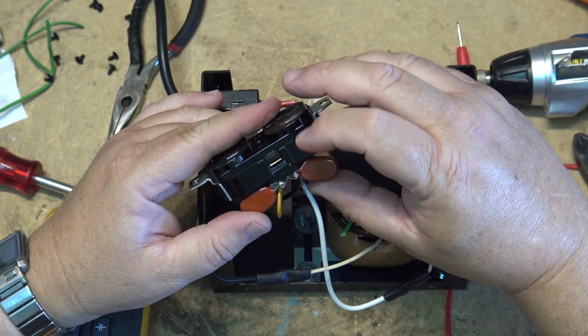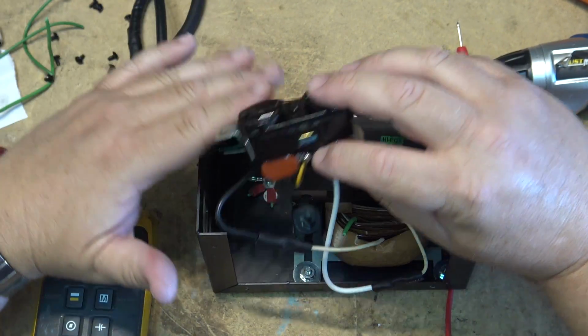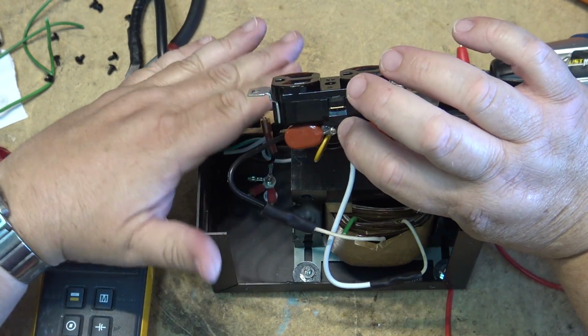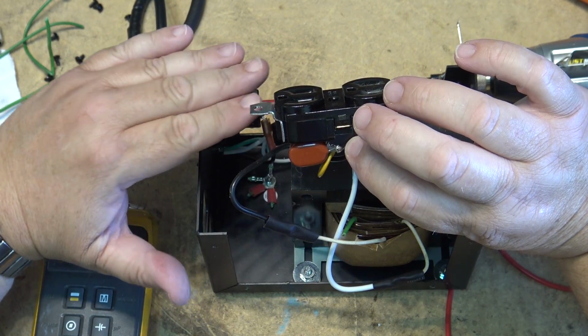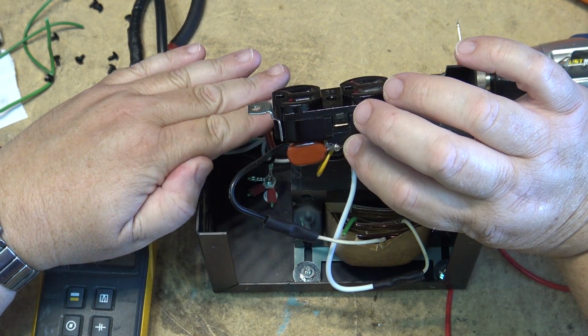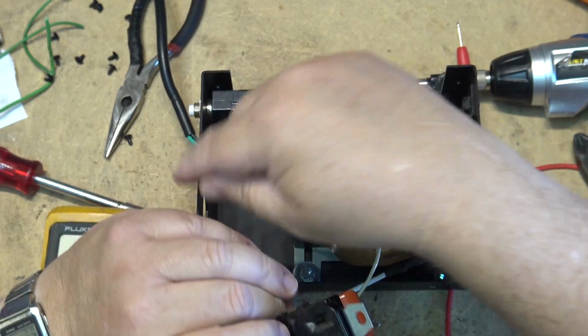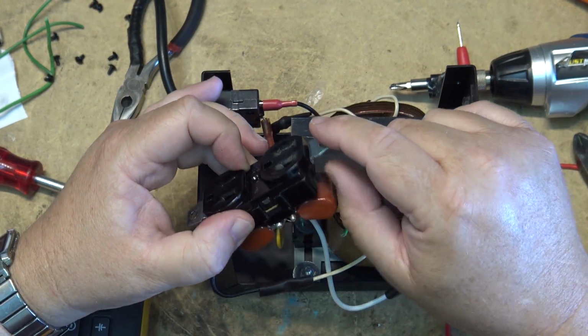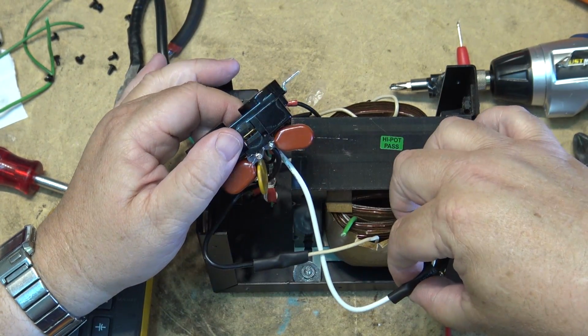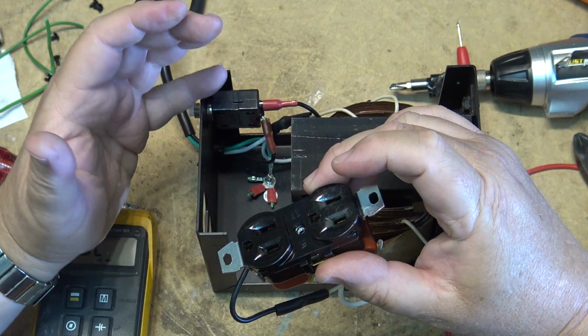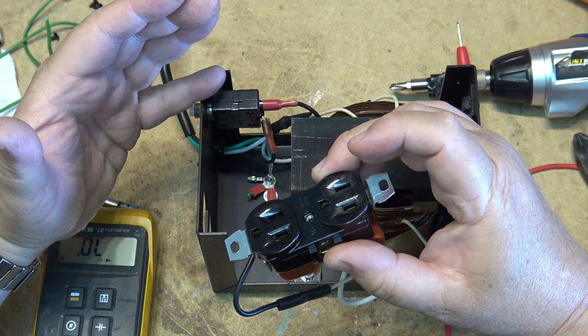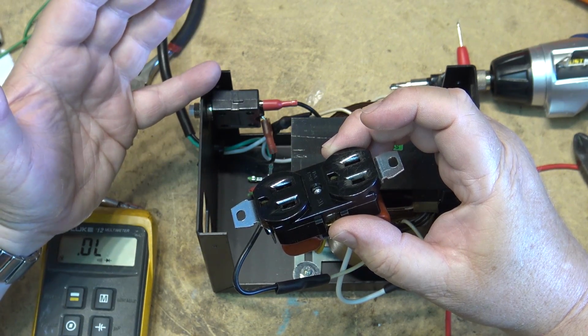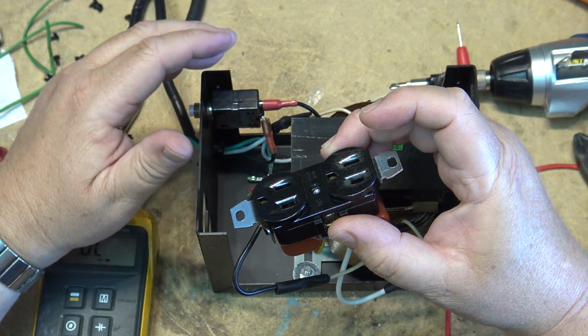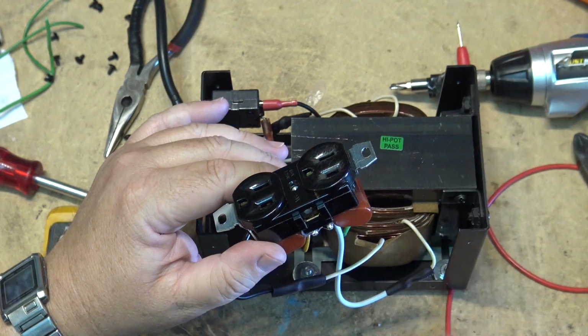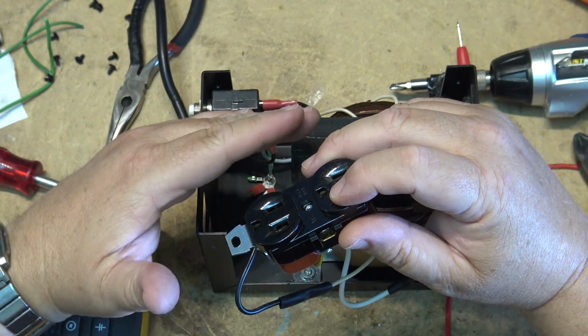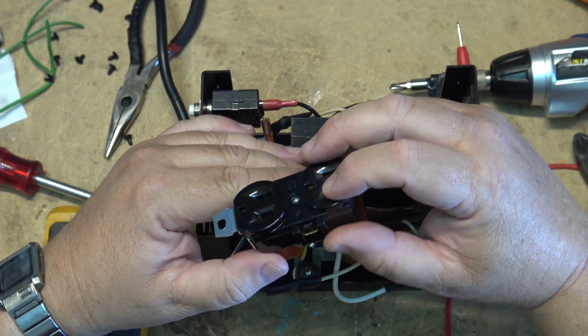the short prong, basically the black wire on a conventional outlet, and they are grounded, the current will flow from the line through the person to ground and can electrocute them. And the same thing would happen with the ground wire attached to the ground prong on here, and by means of the neutral wire, which was also grounded. This basically defeats the purpose of having the transformer to begin with. If you're passing your ground through from the line side to your load, you're defeating the reason that you're putting the transformer in, which is to provide the user with safety, isolating them from accidental contact with mains voltage.